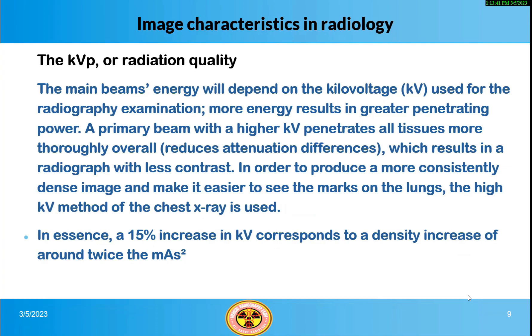The main beam's energy will depend on the kilovoltage (kV) used for the radiography examination — more energy results in greater penetrating power. A primary beam with a higher kV penetrates all tissues more thoroughly overall, reduces attenuation differences, which results in a radiograph with less contrast. In order to produce a more consistently dense image and make it easier to see the marks on the lungs, the high kV method of the chest x-ray is used. In essence, a 15% increase in kV corresponds to a density increase of around twice the mAs.